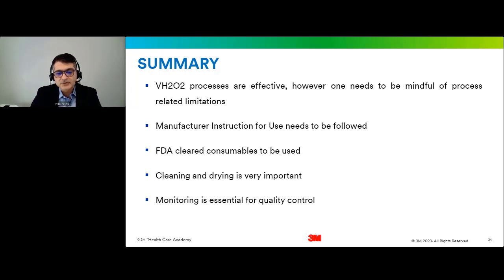Use FDA-cleared consumables for hydrogen peroxide systems. When the consumables get FDA clearance, they are cleared for each specific cycle. If it's listed on the FDA clearance list, then it can be safely used. If not, it has not been tested or validated. Cleaning and drying is very important. Regardless of which modality you use, whether hydrogen peroxide, ethylene oxide, steam, or other modalities, cleaning is a very important and essential step. If it's not cleaned, it cannot be sterilized. So do not forget this baseline.